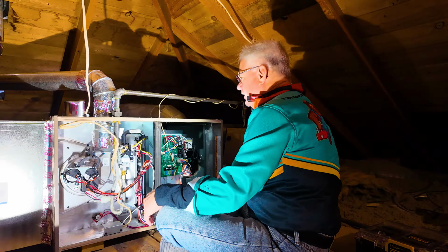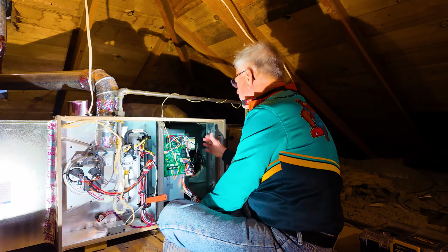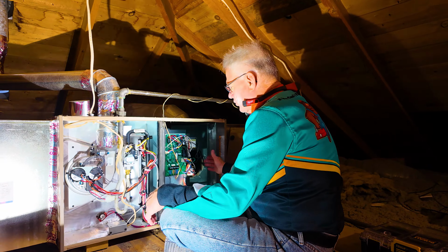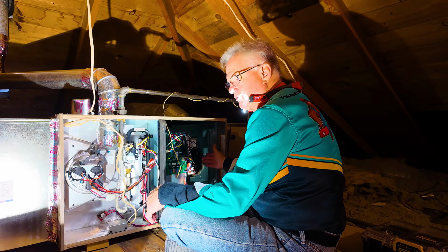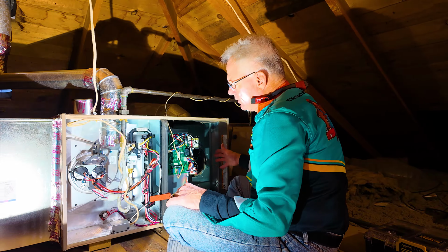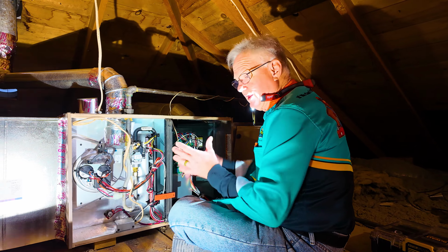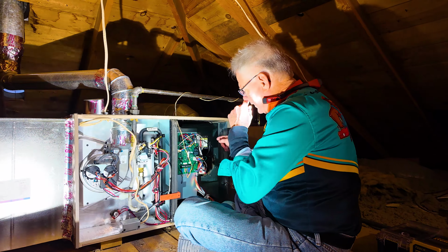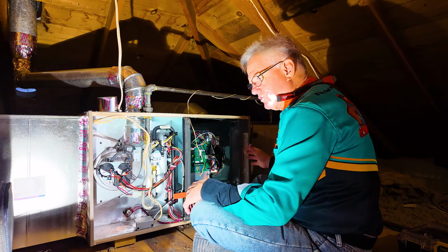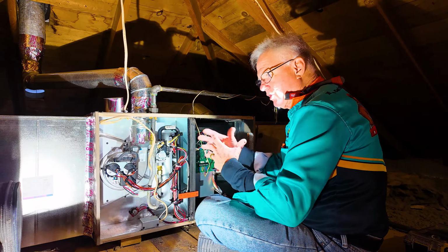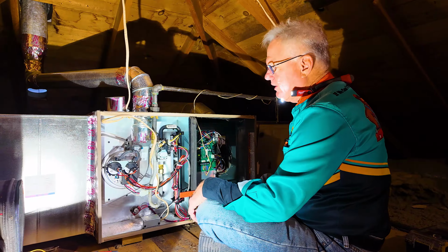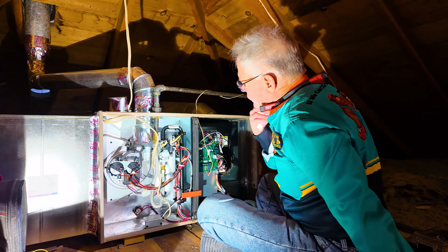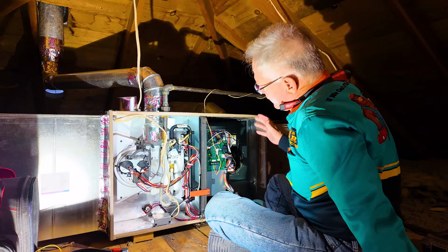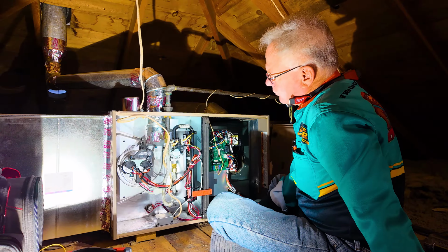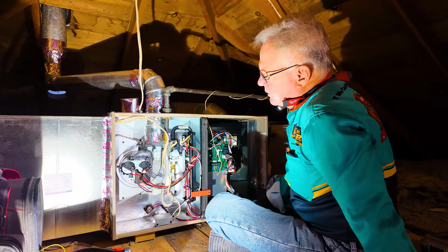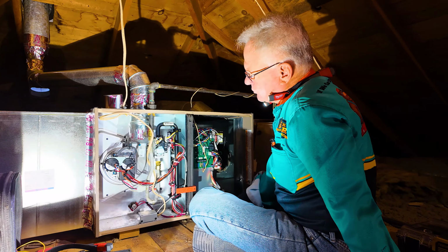Okay, so now the flame's out. Once the flame goes out, the call is gone, then the blower motor keeps blowing so that it will cool down the heat exchanger, because the heat exchanger is hot. So the blower keeps blowing until the heat exchanger cools down, both for safety but also to use that energy and the heat in there that's already been generated and paid for. So it's getting that heat, still blowing it into the house as long as it's not cold already. And that's good for the heat exchanger too.